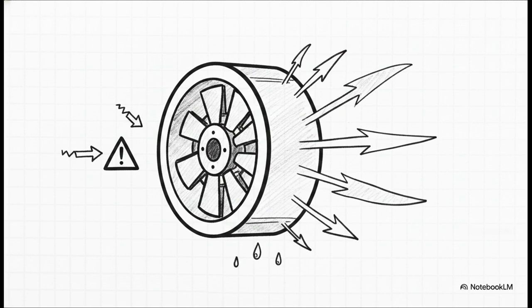We are talking thousands of refrigeration tons in a single unit, with unbeatable energy efficiency at 100% full load. But there's a huge Achilles heel. If the load drops too low, you get a destructive backward flow called surging, which causes extremely dangerous vibrations and requires highly precise control to prevent.